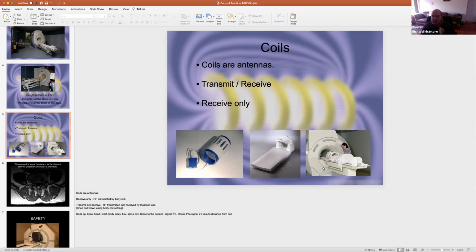There's also a coil inside the machine called a body coil. We can actually scan without our head coil, just scanning a patient lying on the table. The body coil inside puts in the RF to the patient, and then it will listen to that RF. The trouble is that if we use the body coil, the signal between the brain and the body coil is too weak, and you're going to lose a lot of signal. So that's the purpose of having a head coil, a spine coil, a wrist coil, a knee coil, and everything else that we have. They're called local coils. Perhaps we have surface coils which wrap around a knee or wrap around a limb.